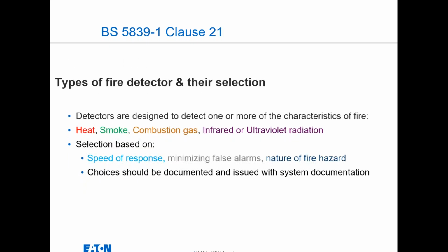Well, types of fire detectors, we touched on some of them earlier, and their selection process. So you've got heat, smoke, combustion gas, infrared, UV, and the selection is based on the speed of response needed, minimizing false alarms within that space, and the nature of the actual fire hazard. So whether that's a chemical fire, a slow burn fire, etc. And the choices should be documented and issued in the system documentation.